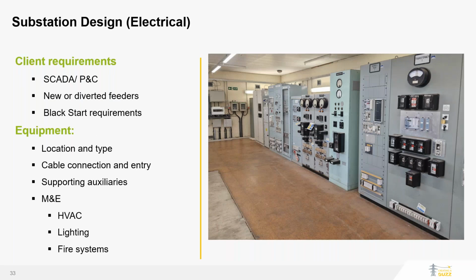When we move from feasibility to detailed design, client requirements really become more prevalent. So we need to look at what type of protection and control is required. This is the point where collaboration and civils designers and other disciplines become essential. When looking at equipment type and location, we need to consider cable routing and entry. Does the equipment require additional cable support? Can we maintain the clearances that are mandated by the utility standards? Appropriate separation between equipment, i.e. the separation of transformers and switchgear and battery chargers, to name a few.